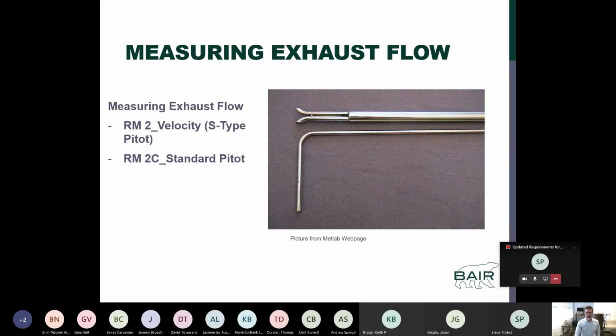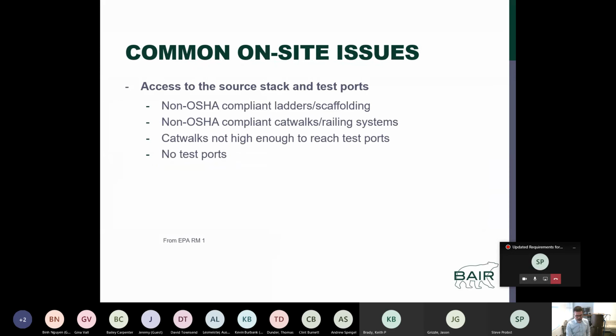Your other option, again, for coming up with exhaust flow is to measure it directly. And so two methods, essentially, Method 2, and there are variations of Method 2, like Method 2C. For the purposes of engine testing, these are the two methods you would use. Method 2 is for stacks that are typically larger than 12 inches in stack diameter. Method 2C is for your small diameter stacks, less than 12 inches. And there are two different types of pitots that you would use. The top one here is for large stacks. That is what's known as an S-type pitot. The pitot at the bottom is a standard type pitot used for the smaller diameter stacks. And I've got this mock stack behind me, and we'll show some examples here shortly.